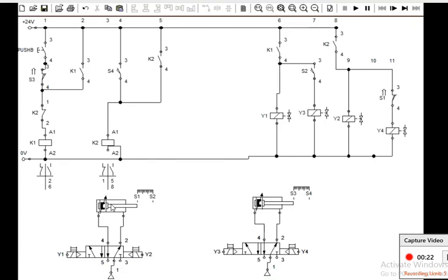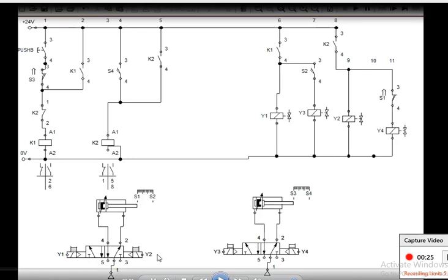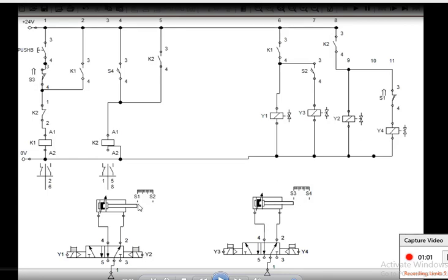The sequence I want is A plus B plus A minus B minus. For that I have put solenoids Y1, Y2, Y3, and Y4. When Y1 solenoid gets current it gets actuated and the A plus operation happens — the piston at S1 moves to S2. When B plus operation happens, Y3 solenoid gets actuated and the piston moves from S3 to S4. For B minus, Y4 solenoid gets actuated and moves from S4 to S3; for A minus, Y2 solenoid moves the piston from S2 to S1.